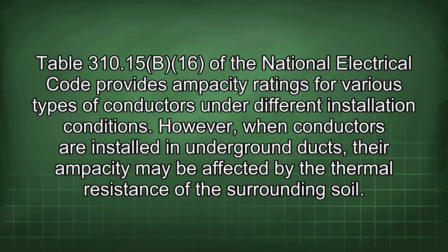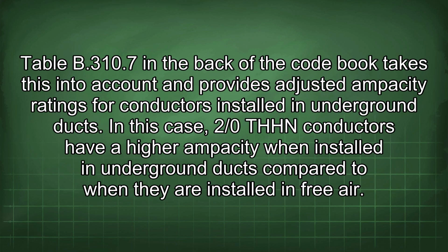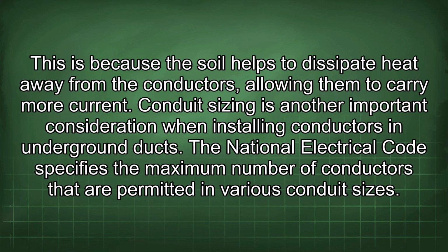However, when conductors are installed in underground ducts, their ampacity may be affected by the thermal resistance of the surrounding soil. Table B.310.7 in the back of the codebook takes this into account and provides adjusted ampacity ratings for conductors installed in underground duct. In this case, 2/0 THHN conductors have a higher ampacity when installed in underground ducts compared to when they are installed in free air. This is because the soil helps to dissipate heat away from the conductors, allowing them to carry more current.